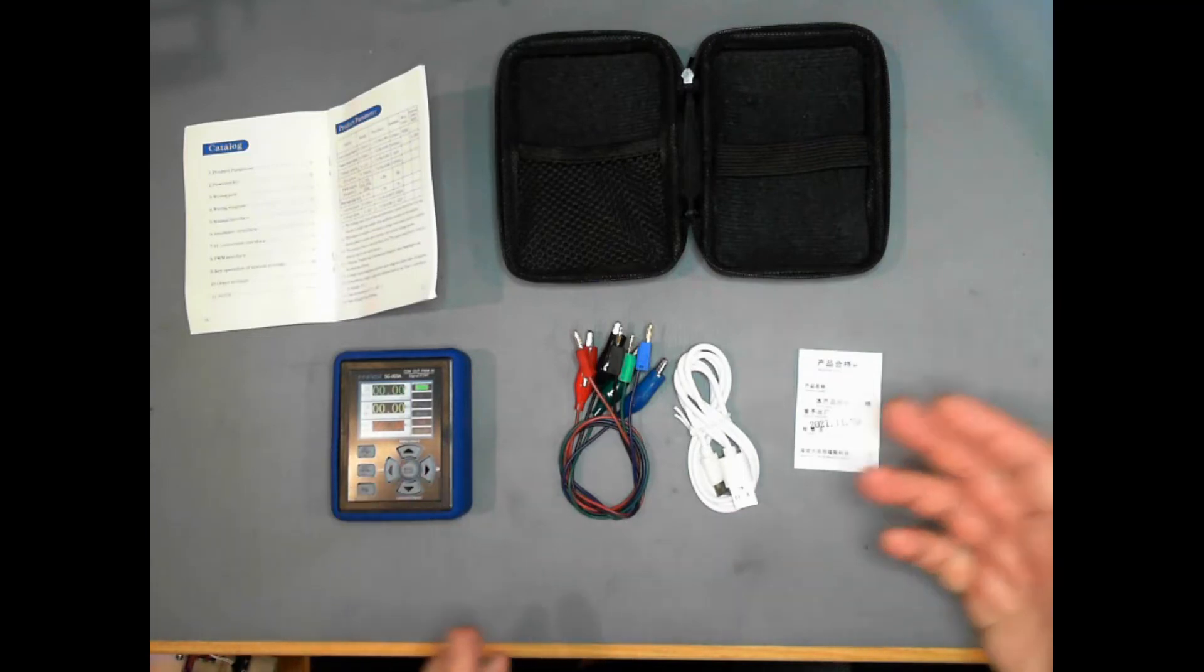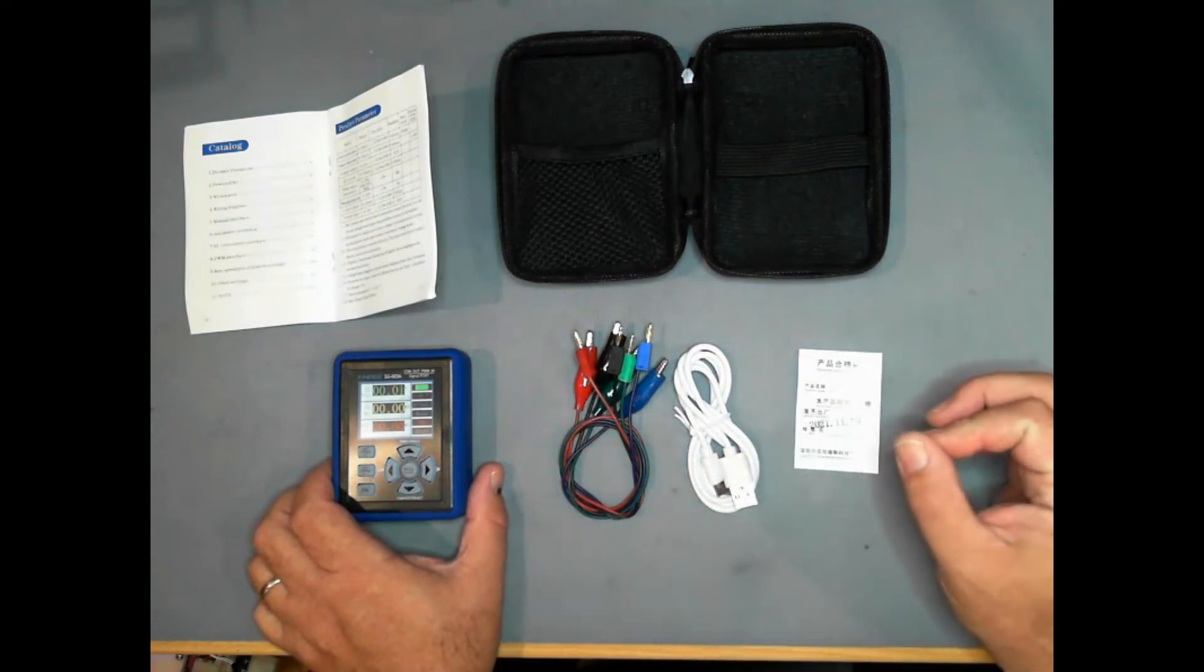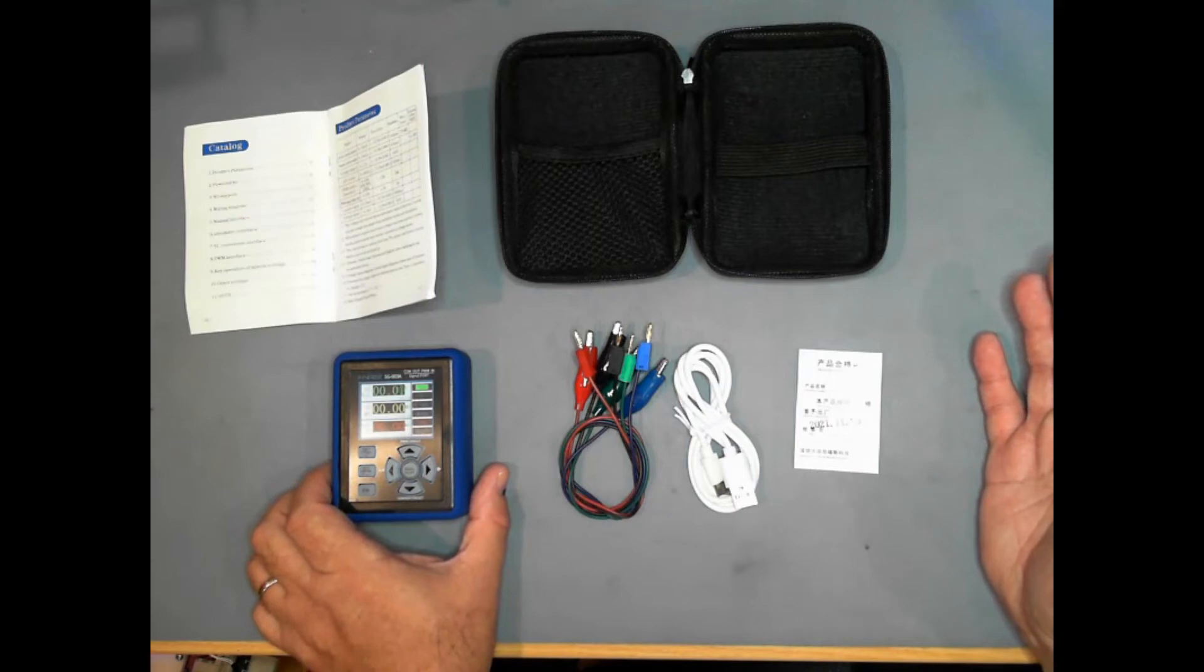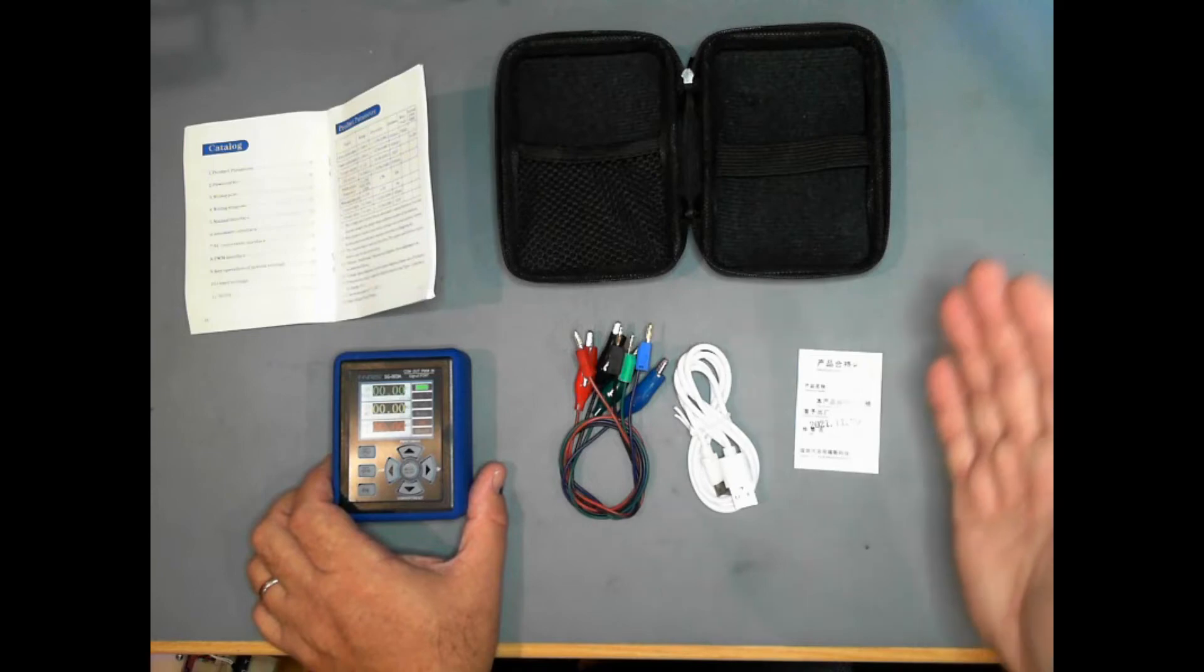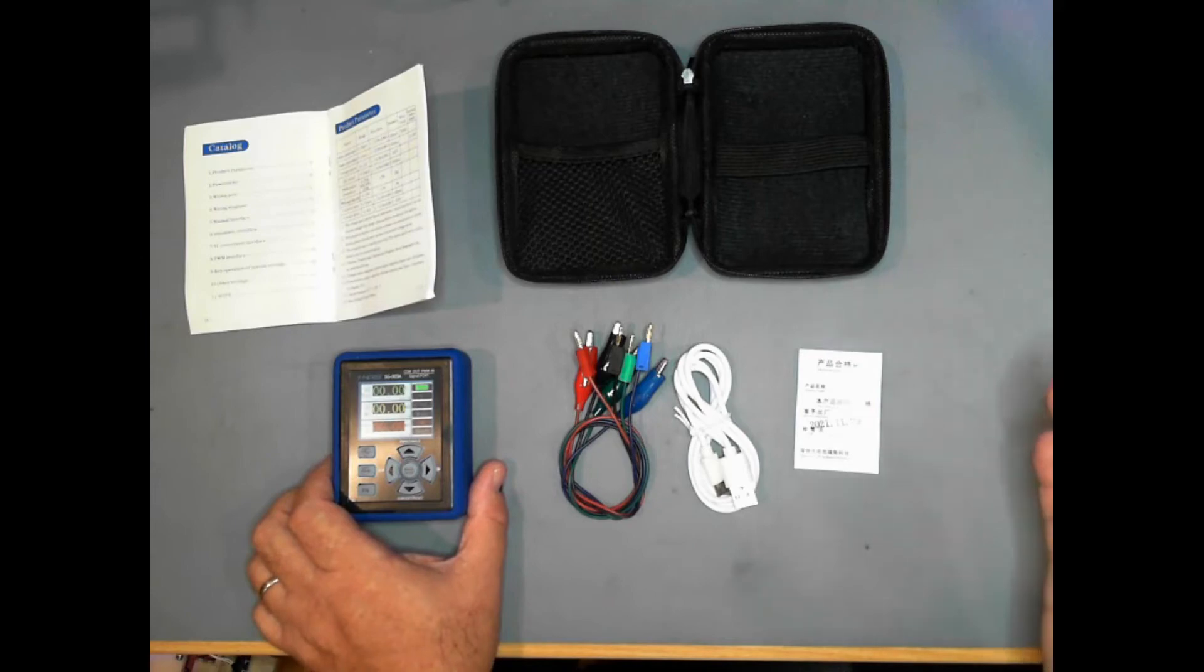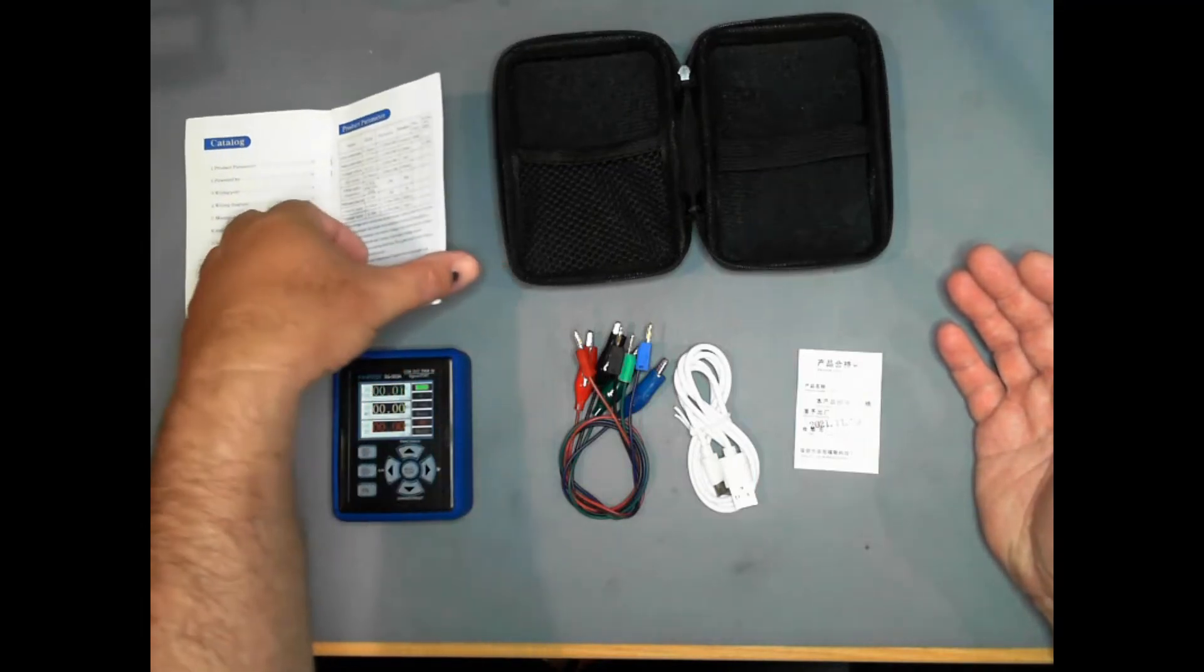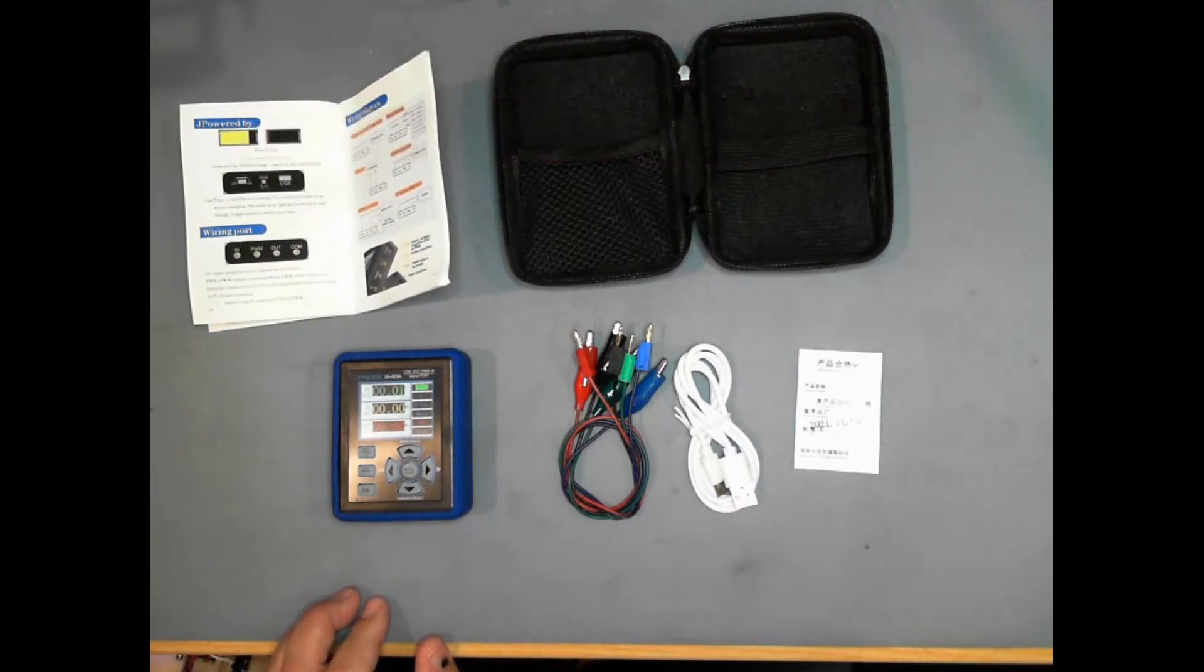24 volt off, reading in milliamps, this is where you can turn the output on. You can actually get it to output 24 volts through the loop and it'll measure the current flowing through that. That's where it becomes really handy for testing a sensor that's 4 to 20 milliamp loop powered. There are a lot of sensors out there that are like that. The before mentioned pressure transducers, I have seen ultrasonic, radar or ultrasonic range sensors, radar range sensors that are all loop powered. This works really well for that sort of thing. It wasn't an overly expensive tool, I will put the cost in the description when I find it again.